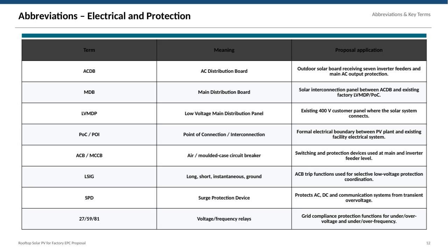Here we have key abbreviations and terms related to electrical systems and protection, specifically for our rooftop solar PV proposal for the factory EPC project. Starting with ACDB, which stands for AC Distribution Board. This is the outdoor solar board that receives 7 inverter feeders and provides the main AC output protection. Next is the MDB, or Main Distribution Board, acting as the interconnection panel between the ACDB and the existing factory's low-voltage main distribution panel, or LVMDP.